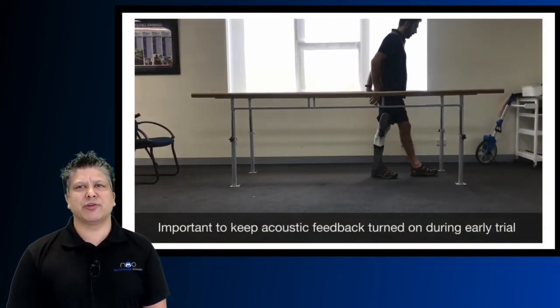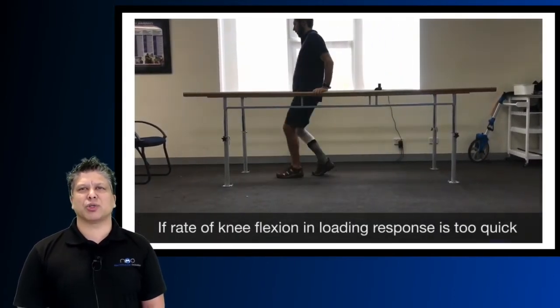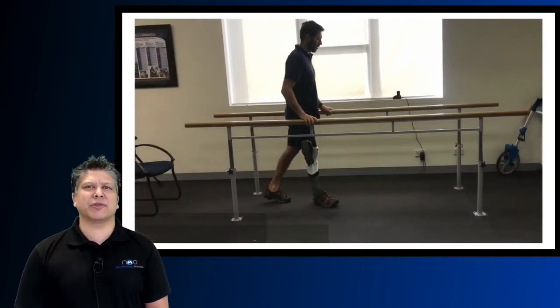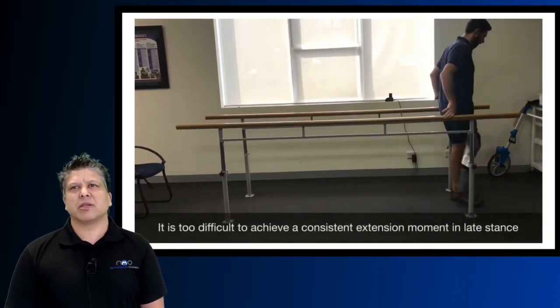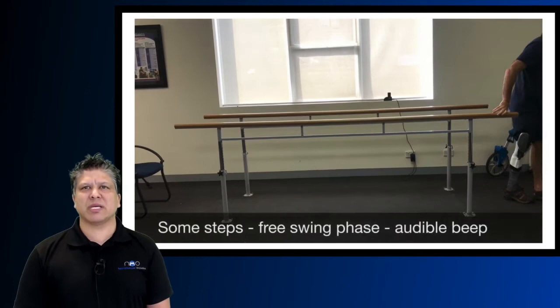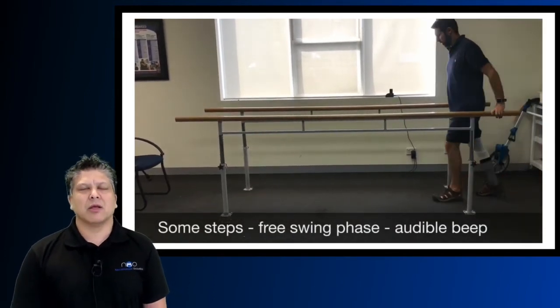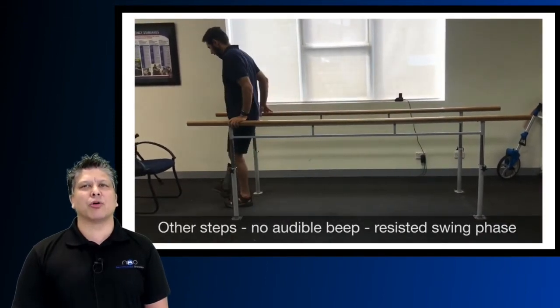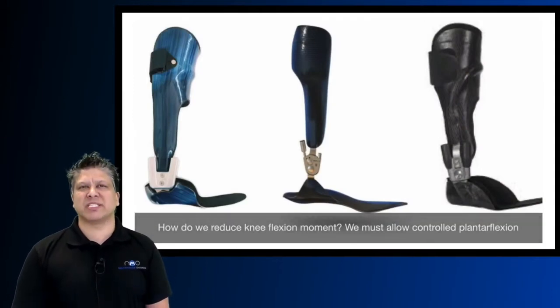It's important to keep acoustic feedback turned on during the early trial. If the rate of knee flexion in loading response is too quick, the client won't be able to achieve an extension moment consistently. Some steps the client will reach an extension moment and have free swing phase with an audible beep; on other steps the client won't hit that extension moment, there'll be no audible beep, and the leg will swing through with resisted flexion.